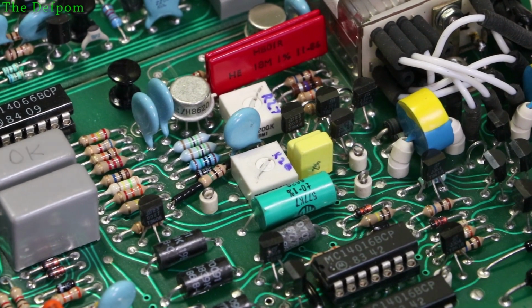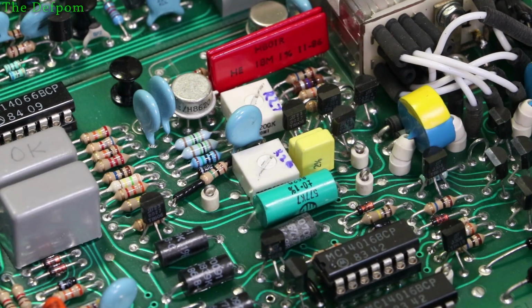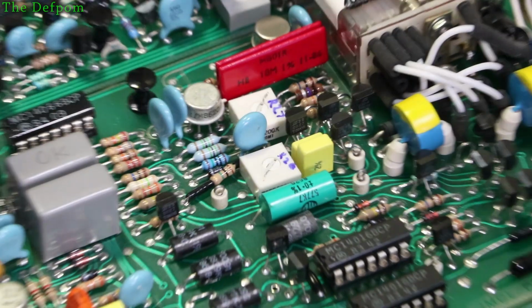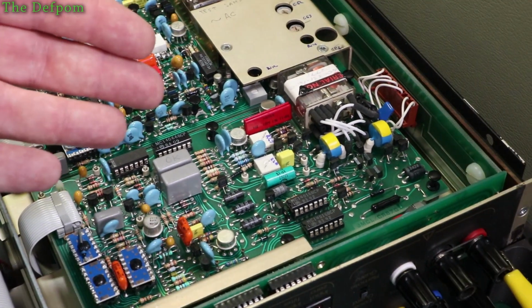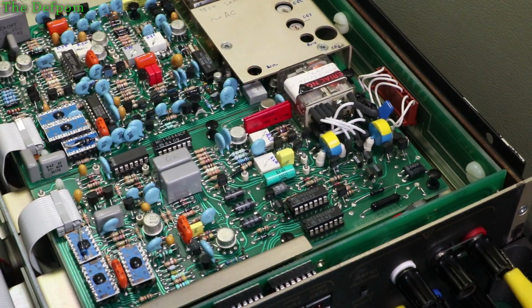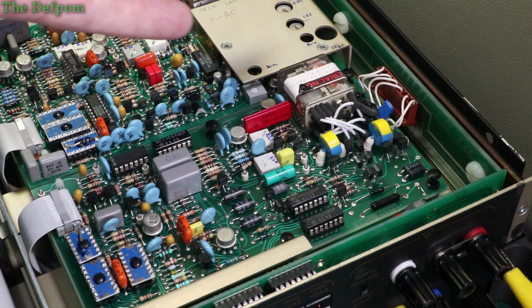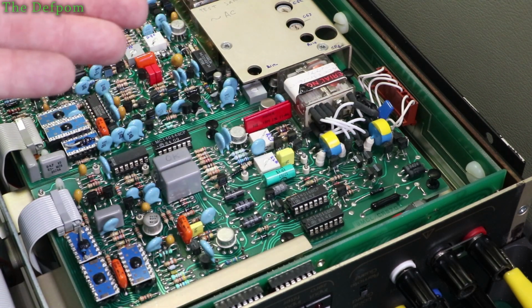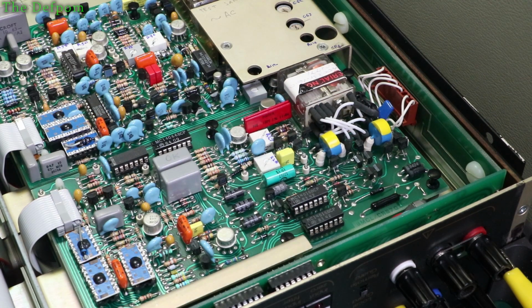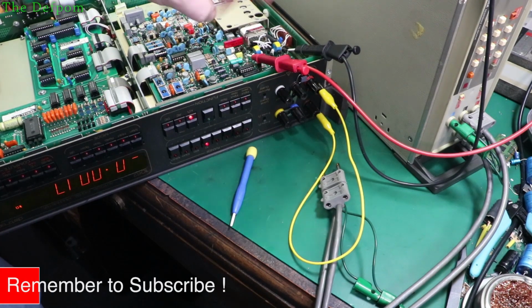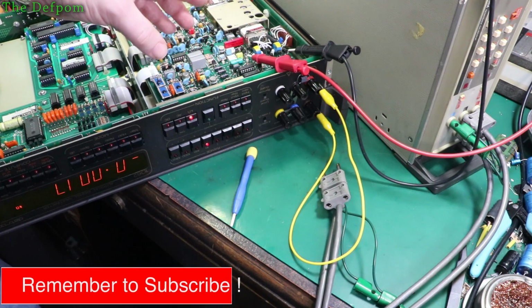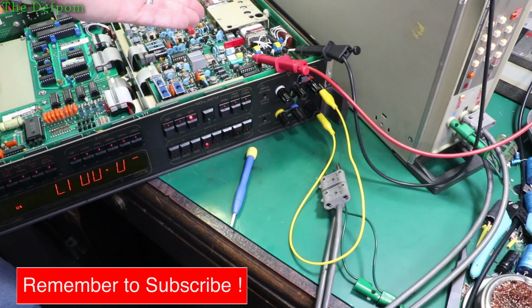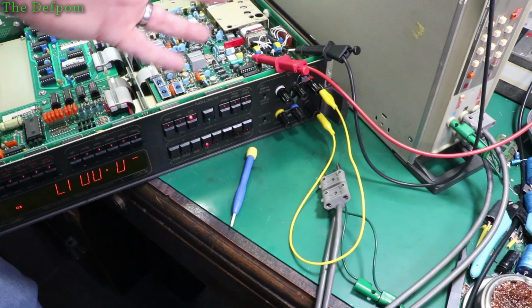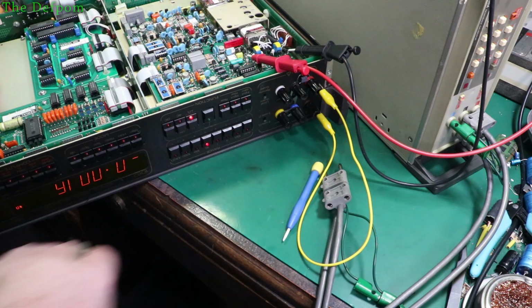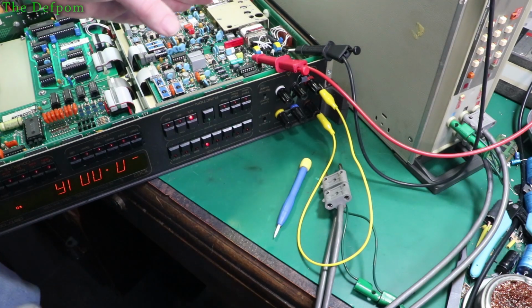I'll go between those 2 steps repeatedly to make sure I've got it completely correct. Obviously one adjustment has an effect on the other adjustment. So I'll go back, recheck the other one, make sure it's still okay. But it probably is, I expect. So I've hooked up onto the other test points. Again, just rechecking that value, and we're at about negative 70 microvolts, so it's still within spec by quite a bit. So that's fine.